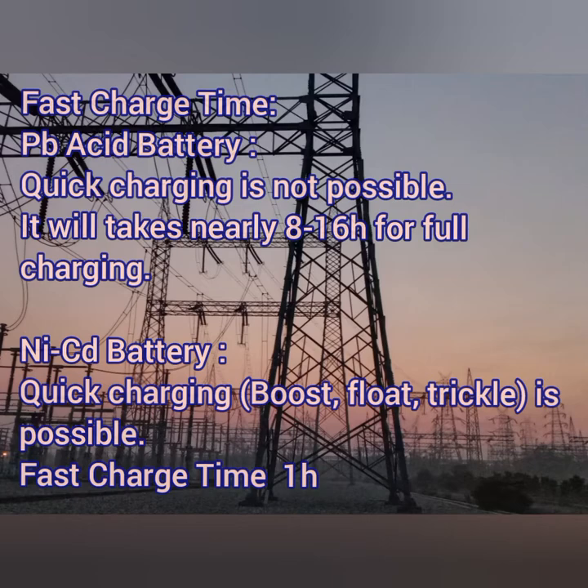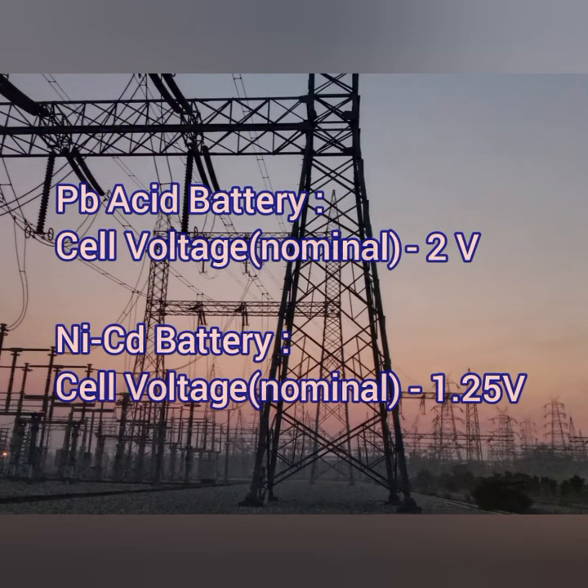Even though nickel cadmium can fast charge, using it in a partially charged condition will also reduce battery efficiency. Next, cell voltage: lead acid batteries have a nominal voltage of up to 2 volts per cell, which can vary from 1.8 to 2 volts depending on the manufacturer. Nickel cadmium batteries have a nominal voltage of 1.25 volts per cell.